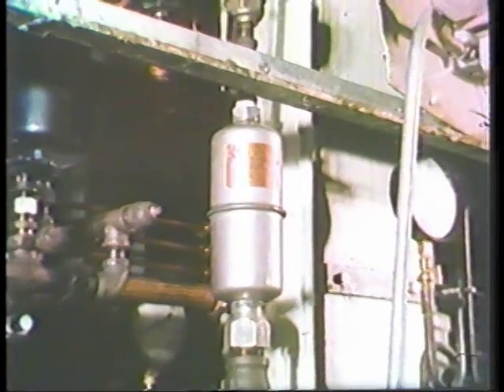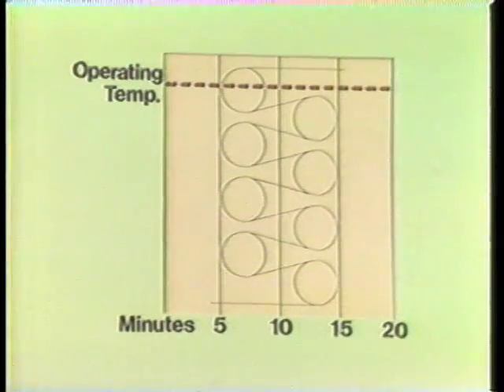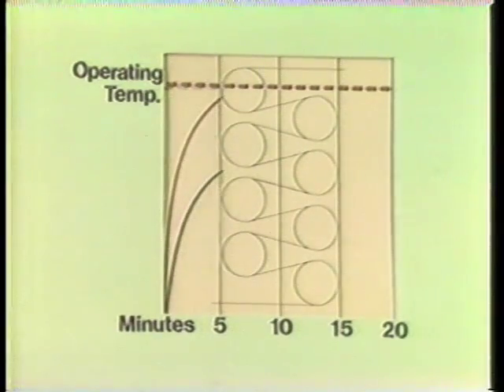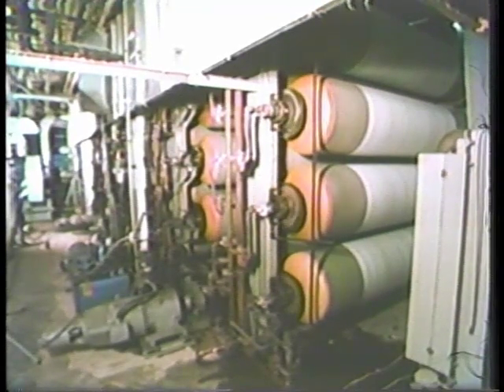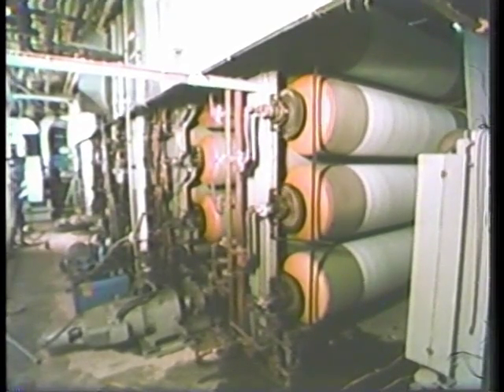Many industries can benefit from installing special air handling devices and other evacuating components on their equipment. In the textile industry, such devices were installed on stacks of dry cans. Initial warm-up time was immediately reduced from an average of 90 minutes to less than 10 minutes. The improved performance resulted in a saving of 4,800,000 BTUs per day in a two dry-can stack — equivalent to 32 gallons of fuel oil or 5,330 cubic feet of natural gas per day.